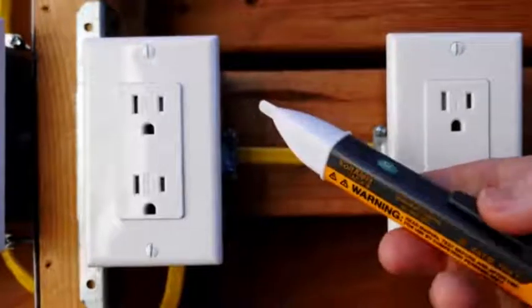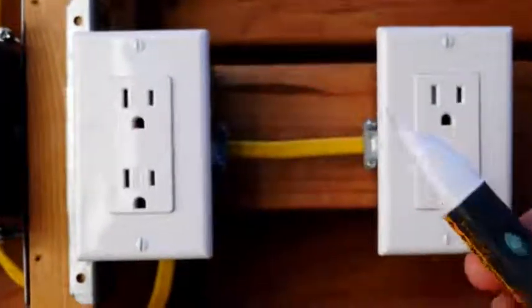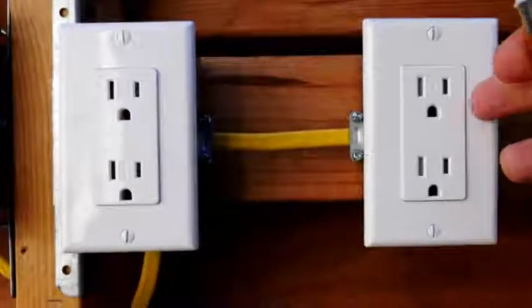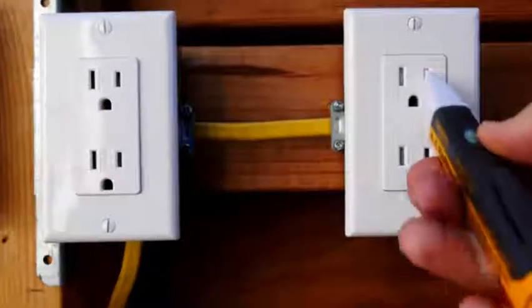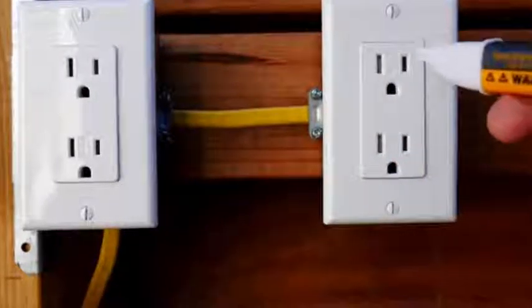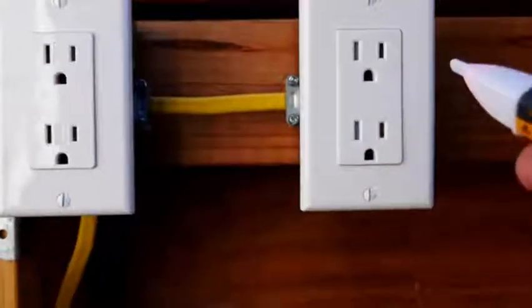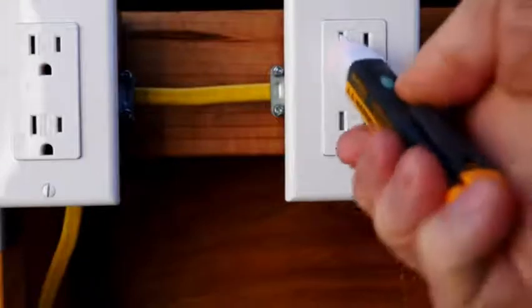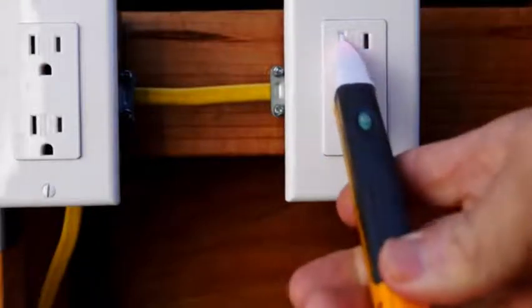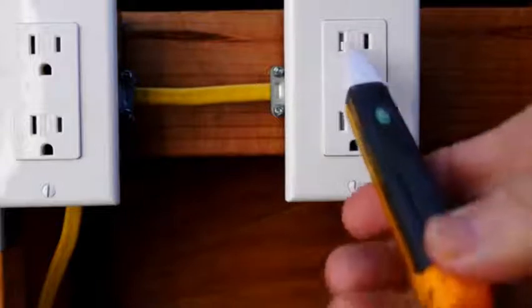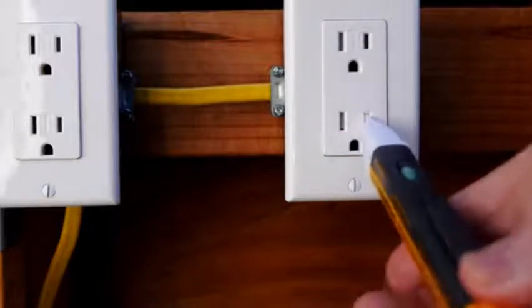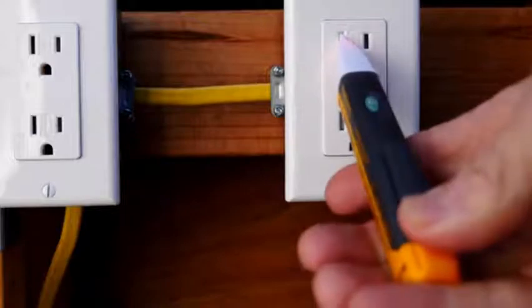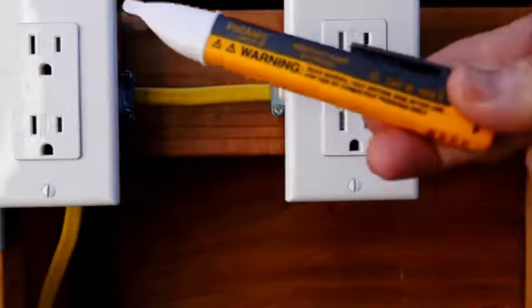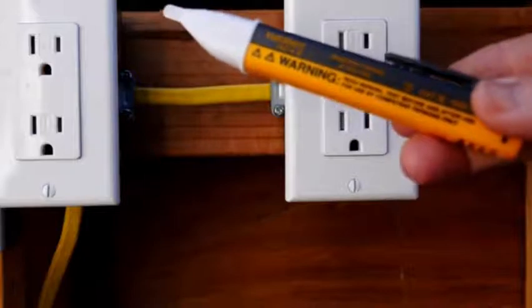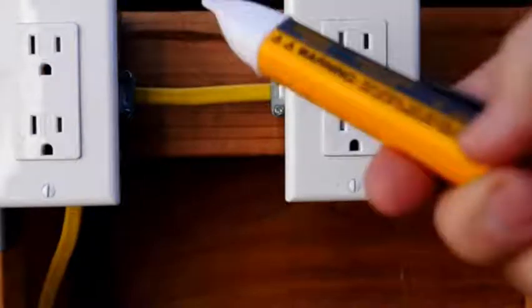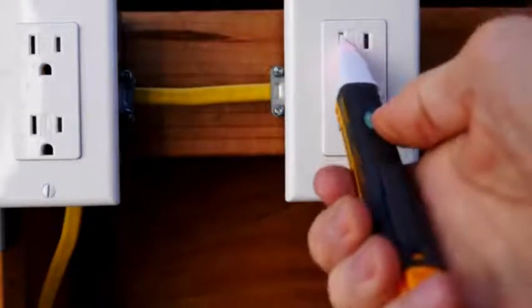Before we get started, I'm going to test my voltage detector. This is an interesting situation because this is a reverse polarity outlet. Normally you would push your voltage detector into the hot positive side of the receptacle, but since this is a reverse polarity receptacle, you actually plug it into the neutral, and you see the buzzer goes and the light goes off. That's another way to tell that this receptacle is reverse polarity. Also, we have tested the voltage detector, which is always a very good idea before you get started, to make sure that your voltage detector is working properly.